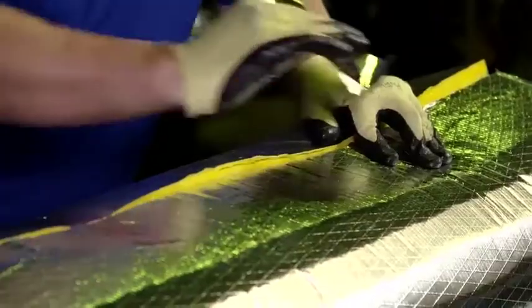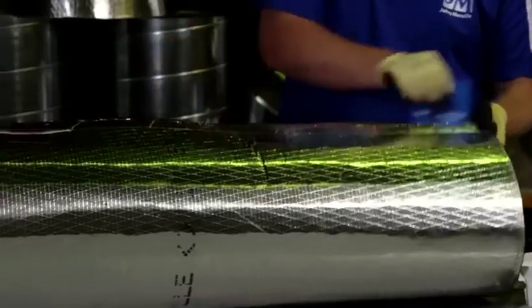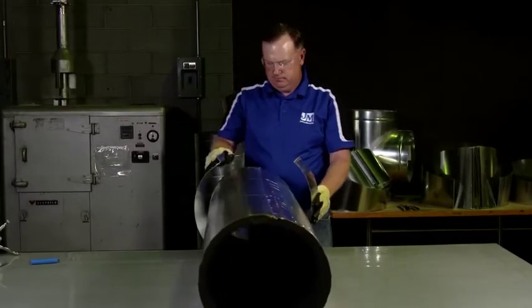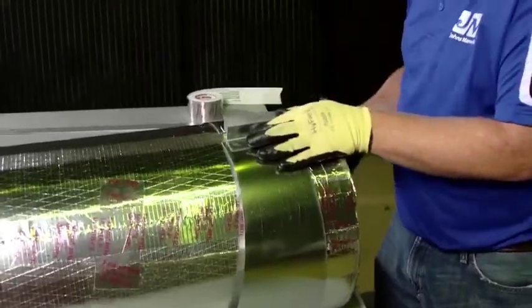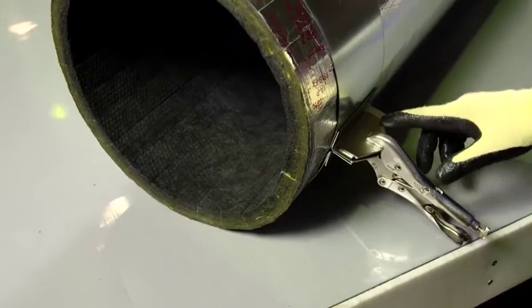From there, roll and tape the insulation as you would for a straight section of duct. Once that's complete, clamp the end gore band around the end of the insulation. Ensure that the clamp of the gore band is not aligned with the seam of the Spiracoustic Plus material.